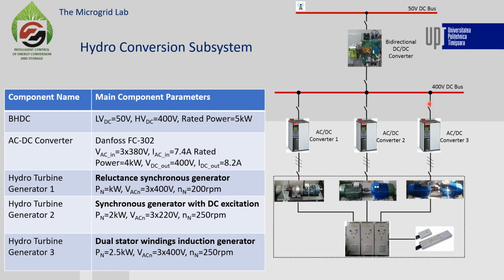Also, in this case, the two DC buses, the high voltage DC bus and the low voltage DC bus, are connected through the bidirectional hybrid switched capacitor converter, which I showed you previously being used for charging and discharging the supercapacitor connected on the high voltage DC bus. But at the moment this schematic was drawn, this converter was used to supply the high voltage DC bus for motor mode operation of the generator.